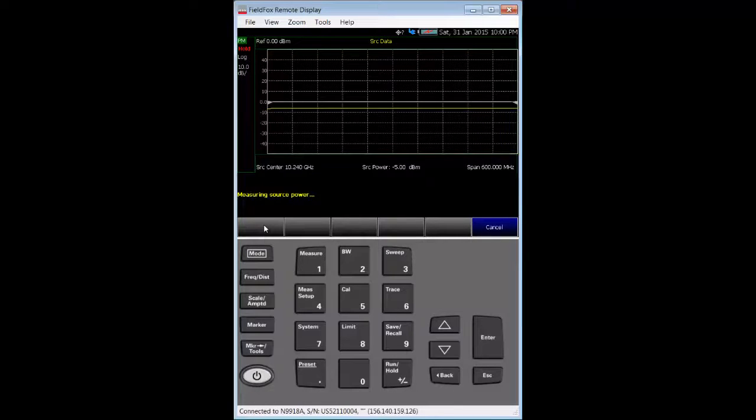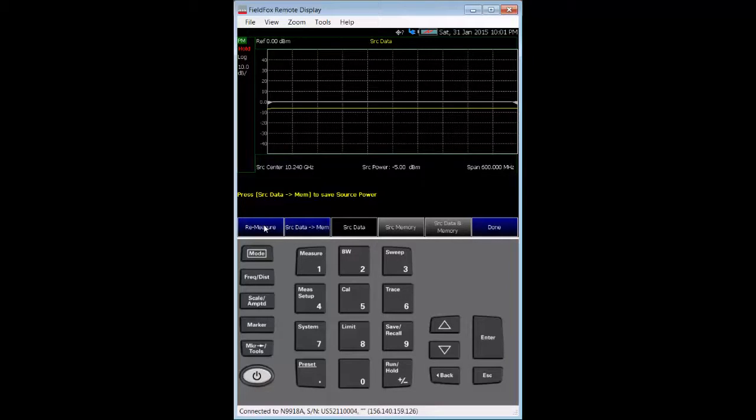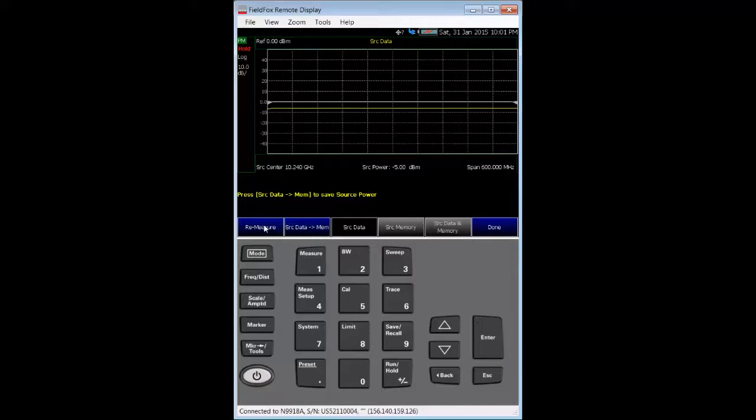The FieldFox source is adjusted to provide a flat minus five dBm signal over the RF input frequency range, ensuring that power flowing into the frequency converter under test is what we set.